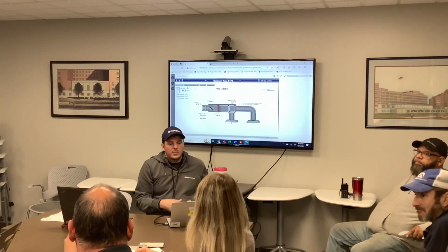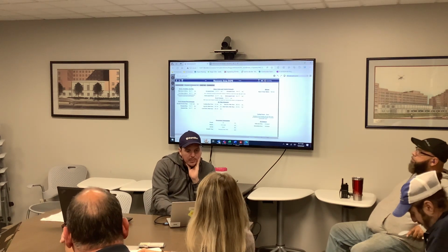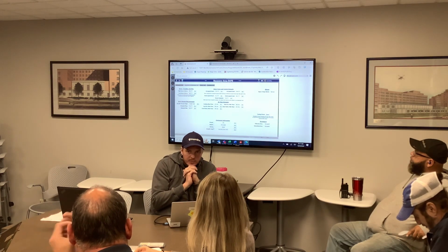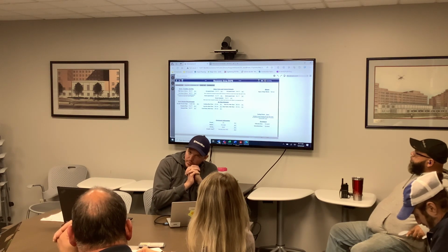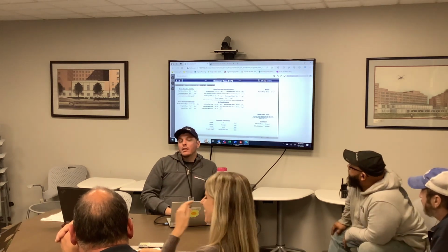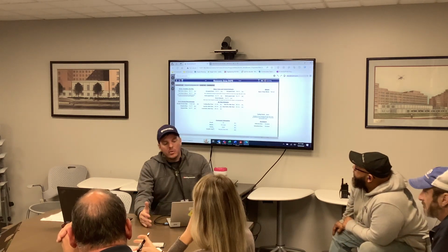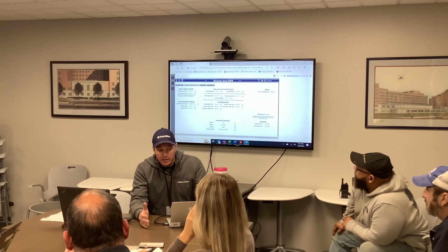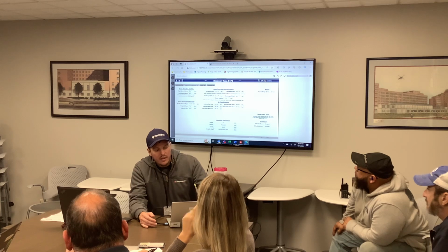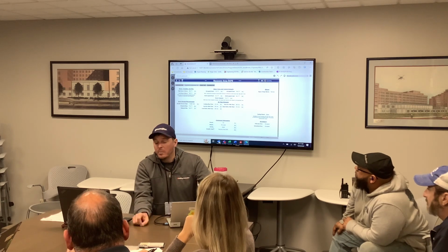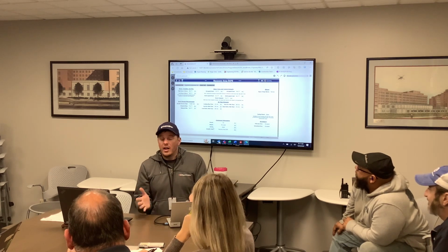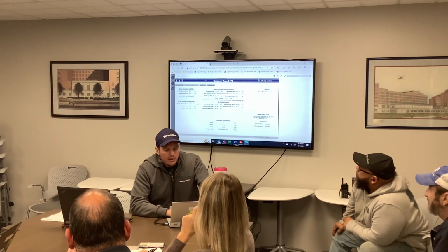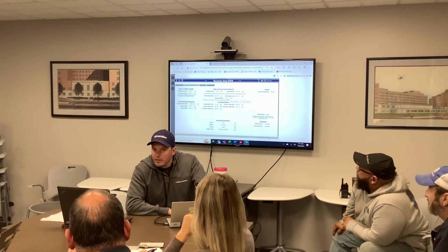One question, I'm back on the set point page. The occupied heat and cool set points, I've noticed they all have lines through them. What's the purpose of that? I don't want you guys touching them, but you can if you want. A lot of people will mess with them and they won't put a deadband in them, and it's stupid enough that it'll let you do that. If you put both on 71 and then lock it up, it doesn't know what mode it's going to switch into. And honestly, you only need to be messing with this room set point anyway.